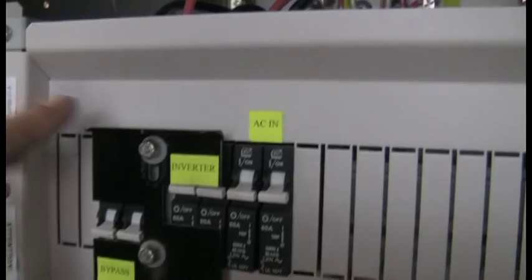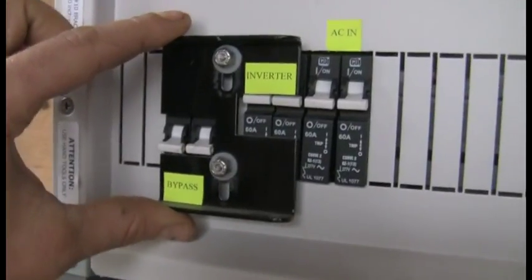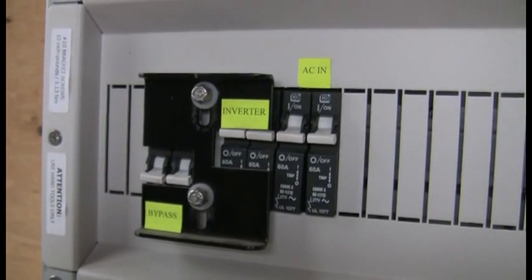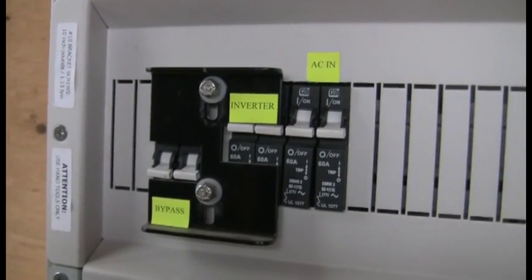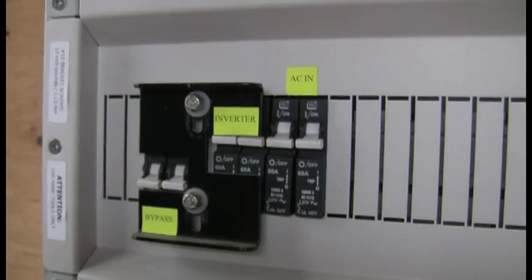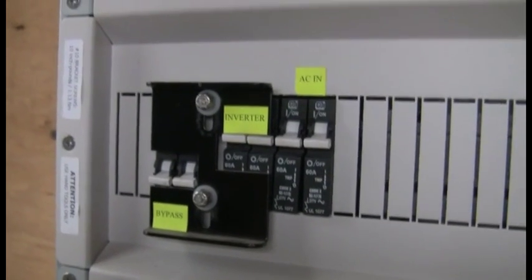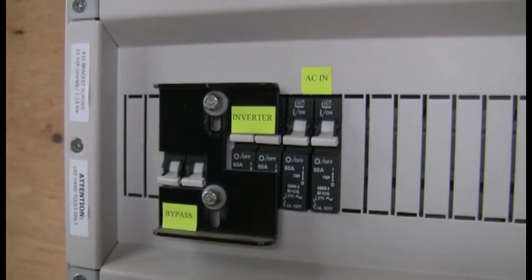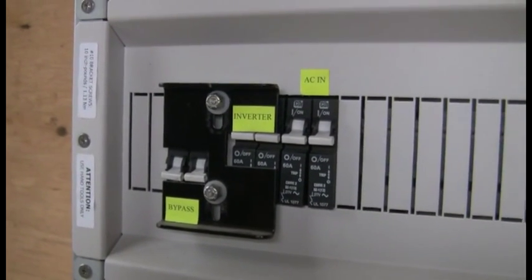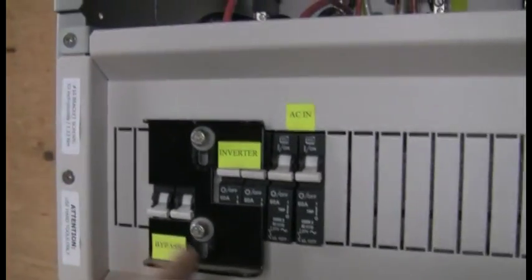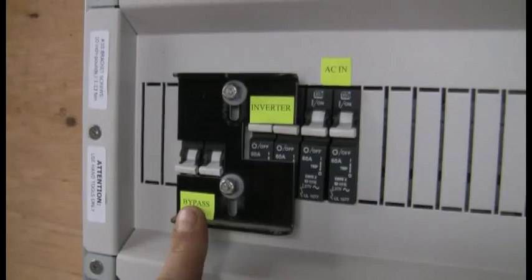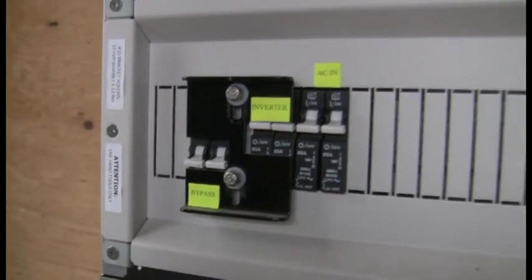If I removed this mechanical limiter, that would allow me to flip both breakers to the on position, which has the effect of back-feeding the residential wiring system. You don't want to do this unless you're absolutely sure that grid power is not present.